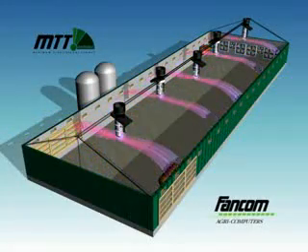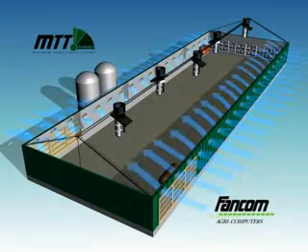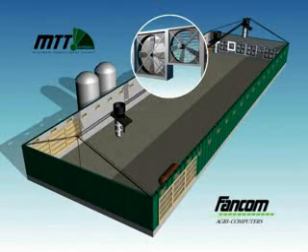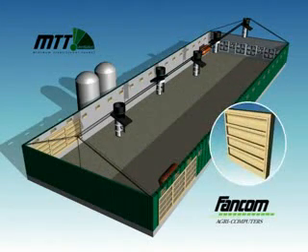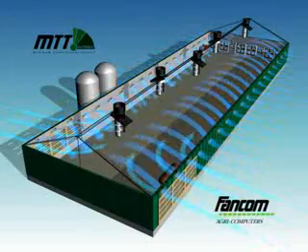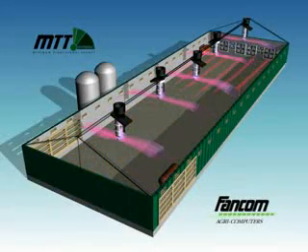If more ventilation is needed, the MTT concept switches over to the transitional phase — the gradual transition to tunnel ventilation. The uninterrupted increase in ventilation prevents disturbances to the airflow. During the transitional phase, minimum ventilation runs at its maximum and the tunnel fans are activated one by one, while the tunnel inlet slowly opens. The airflow gradually changes from minimum ventilation over the width of the house to tunnel ventilation over the length of the house, encouraging the birds to spread well throughout the available space without showing bunching behavior.